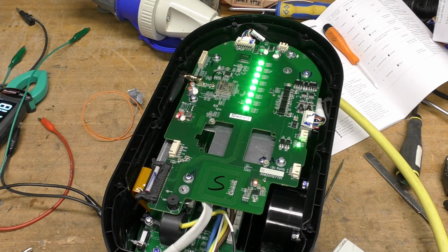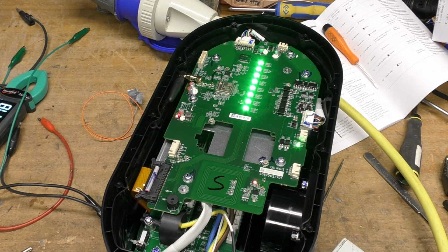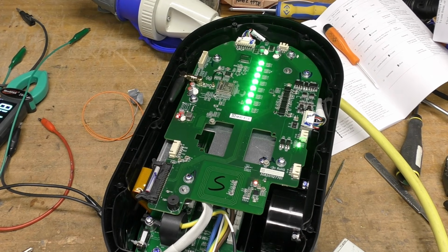So this is why this fault protection is required for EV charge points. More specifically, charge points that are mounted outdoors. This doesn't apply if the charge point is mounted inside a garage in such a way that the cable can't effectively go outside it, but that's a fairly minor case. But generally speaking, all EV charge points in the UK need PEN fault protection. Most charge points sold in the UK have that built in, except there's things like the Tesla where they didn't bother implementing it, so you actually have to use an external protection box in conjunction with those.